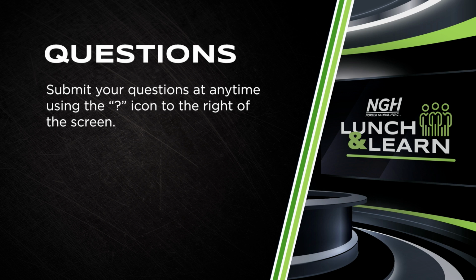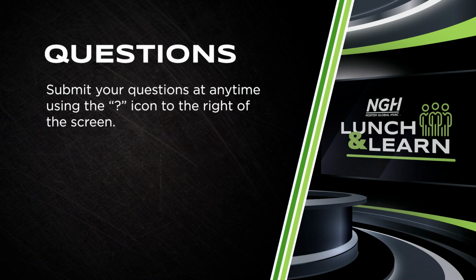So the first question coming in, you said that 410 has similar properties to R454. Can I charge a 410 system with R454? No, you cannot. So yes, the properties are similar, but they're not the same. First of all, the compressors are specific to a certain refrigerant, so you would not get the same performance if you switched gases, as are the expansion devices. But more important than that, an R410A system is not designed to mitigate leaks the way an R454B A2L system is, right? So that has to be in place.